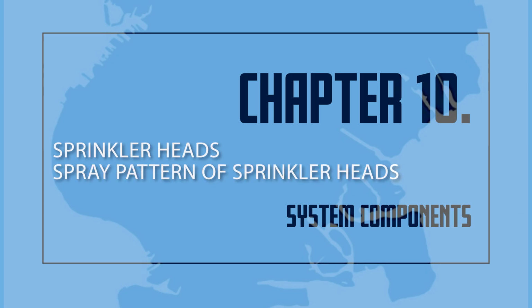Spray pattern of sprinkler heads. The best way to put out a fire is to spray the water from the sprinkler head downward and horizontally. The spray pattern will also prevent the spread of the fire. The force of the water against the deflector creates a heavy spray which is directed outward and downward. The shape of the deflector determines the spray pattern of the water discharged from the sprinkler head. Usually, this is an umbrella-shaped spray pattern. At a distance of 4 feet below the deflector, the spray covers a circular area having a diameter of approximately 16 feet when the sprinkler is discharging 15 gallons per minute. Sprinkler spray patterns must not be obstructed by building components or storage.